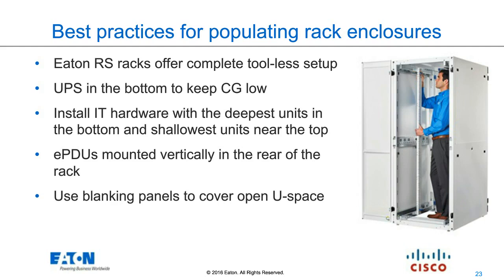We already talked about vertical PDUs in the rear and how they help keep cabling out of the way so airflow isn't dampened by cabling. Then there are blanking panels in the front of the rack. Even without an enclosed cold aisle or hot aisle, it's still good practice to cover unused U space with blanking panels, so you don't get recirculating warm air coming back to the front intake and getting warmed up even further.